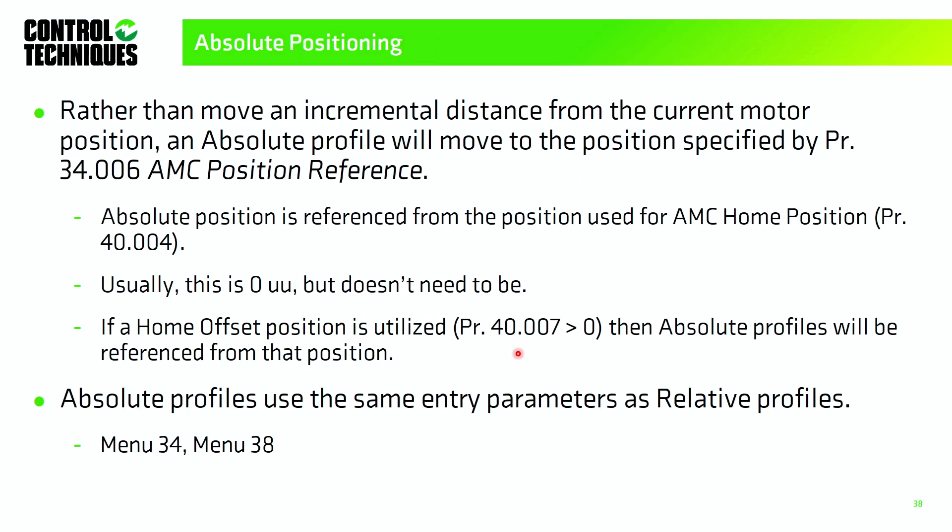The last motion mode is absolute positioning. Rather than moving incrementally from the current position, an absolute profile moves to the position specified by menu 34 parameter 6 (AMC position reference). Absolute position is referenced from the home position. If a home offset is used (menu 40 parameter 7 > 0), absolute profiles reference from that physical position. Absolute profiles use the same parameters as relative profiles — speed and accel/decel in menu 38, position in menu 34.